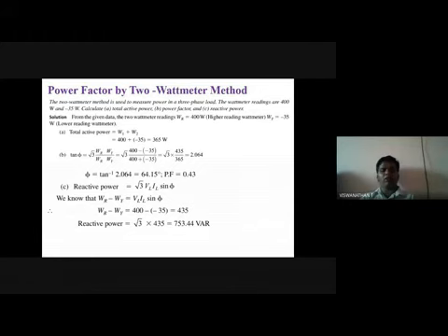So, one problem we discussed. The 2-wattmeter method is used to measure three-phase power. The first wattmeter measures 400 watts, and the second wattmeter measures minus 35 watts. You should be careful with notations. Then calculate the total active power, which is the summation of these two. Reactive power is the difference between those two wattmeters. Then the power factor and reactive power.